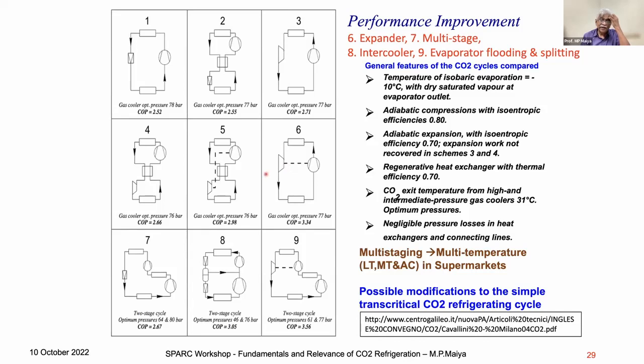But when the expander is there, then the internal heat exchanger will not give a benefit, because you can see here with both together you can go only to 2.98. When you remove the internal heat exchanger, COP increases further. So you can't say that the IHX always improves the efficiency. You can't say, but in general, yes.